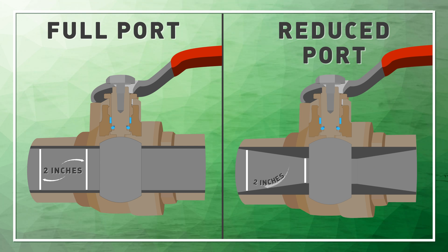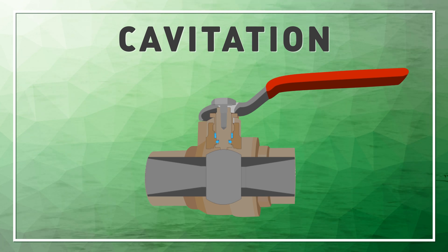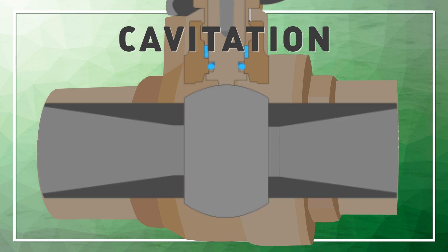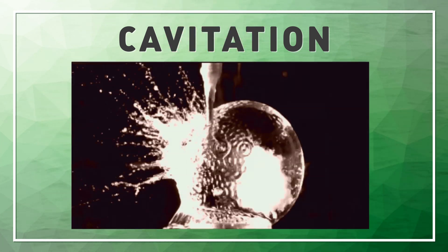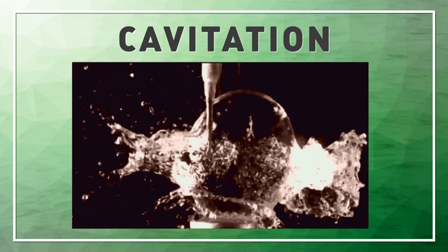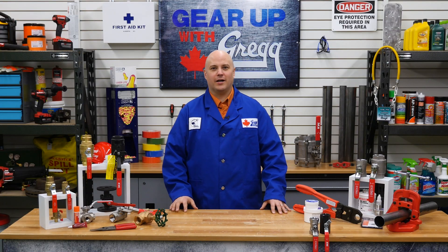Full port valves are more sought out because reduced port valves are more vulnerable to cavitation. Cavitation is a result of change in diameter inside the reduced port, which creates pressure drops, forming vapor bubbles. Once the pressure recovers downstream, the bubbles will begin to collapse, returning to a liquid state, and although this may sound harmless, the constant implosion of the bubbles releases energy and over time will damage the structure of the valve and pipe.